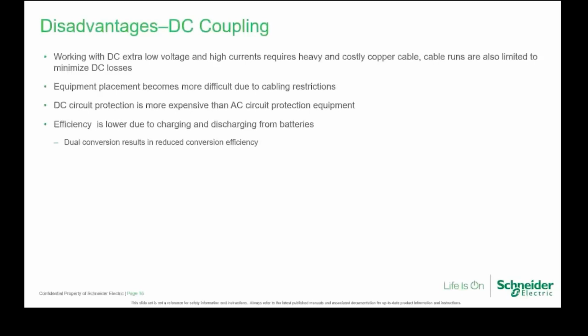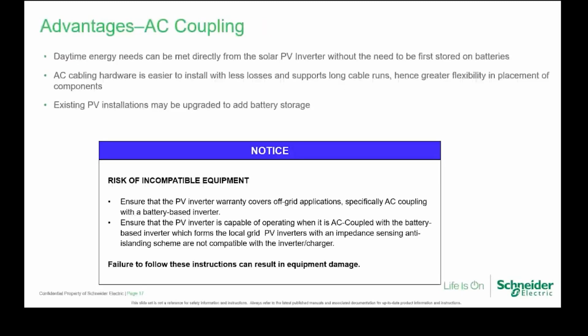When we look at the AC coupling advantages, basically, if you've got daytime energy needs, they can be met directly from the solar PV inverter without the need to be first stored in the battery, which means you don't have to actually go into the XW to store them. You just go straight from the PV inverter into the loads. Obviously, AC coupling hardware is easy to install with less losses and supports long cable runs because you're working at a higher voltage. You have greater flexibility in the placement of the components. And you can use existing PV installations to upgrade the system to add battery storage.